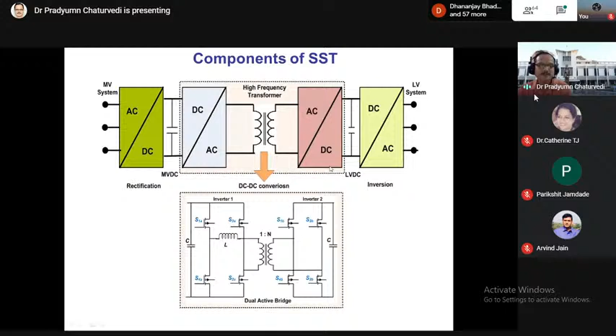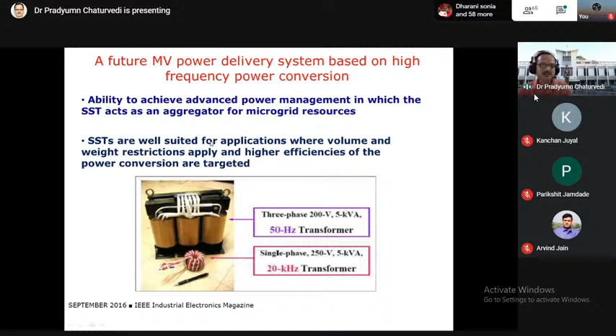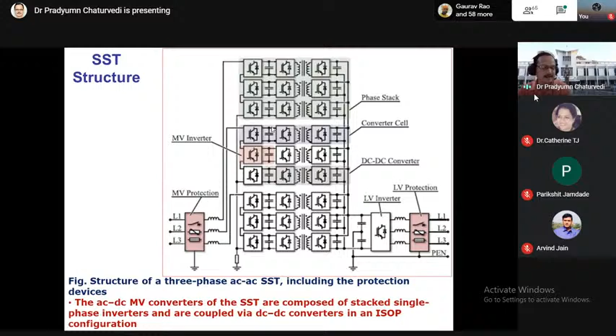It should be able to provide voltage balance control at each DC link. It is a very difficult task to make balanced voltage in such type of applications. Such applications give you so many advantages, but at some point you have to take care, because slight mismatch in the voltage at each DC link here or here will create huge problems of power quality, harmonics, and everything, or losses, stress on the device also, everything.